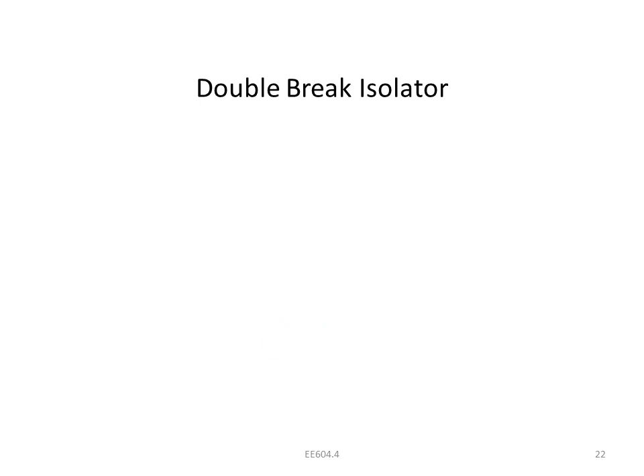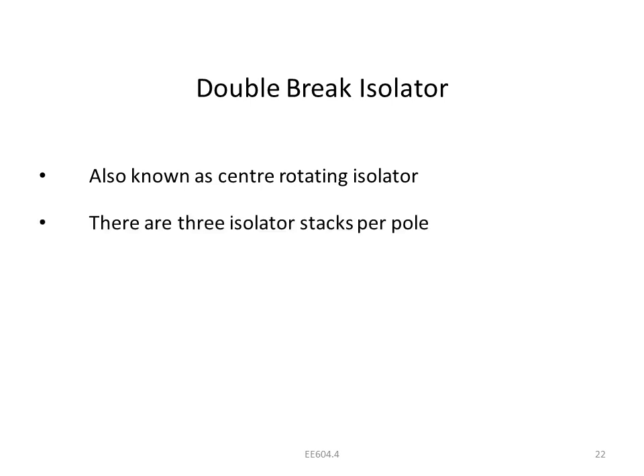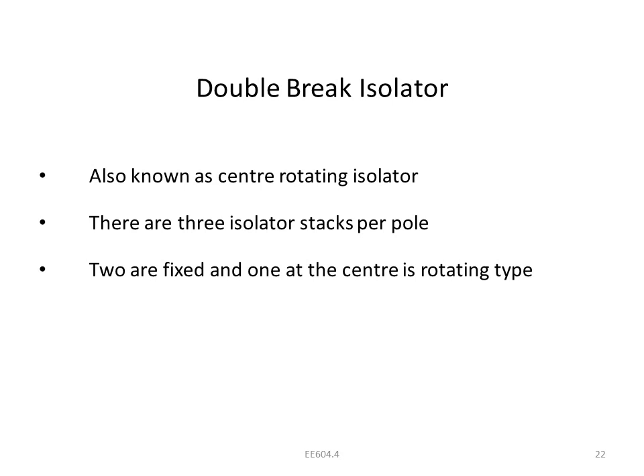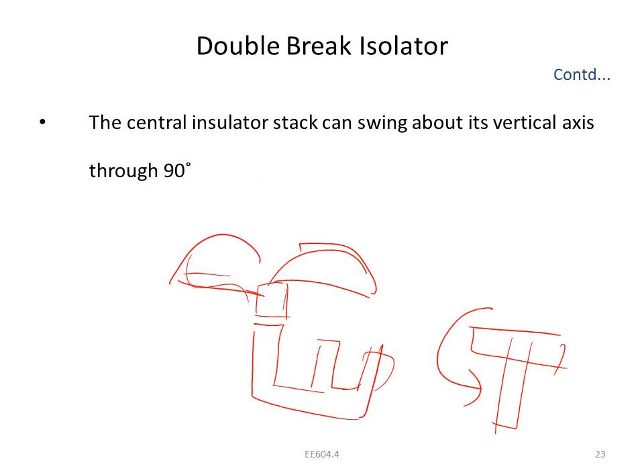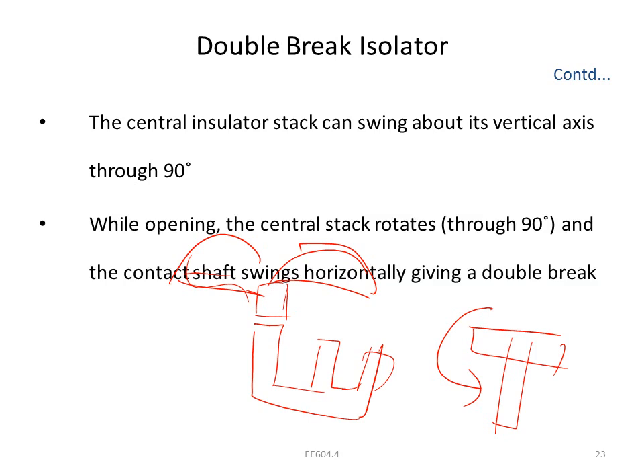Now coming to the double break isolator, which is also known as a center rotating isolator. It has three stacks per pole, two of which are fixed, and the one at the center is the rotating type. The center insulator stack can swing about the vertical axis through 90 degrees. While opening, the center stack rotates through 90 degrees and the contact shaft swings horizontally to make the break.